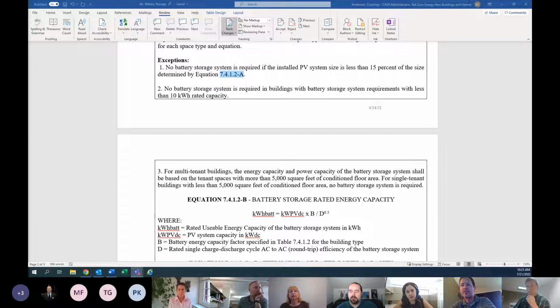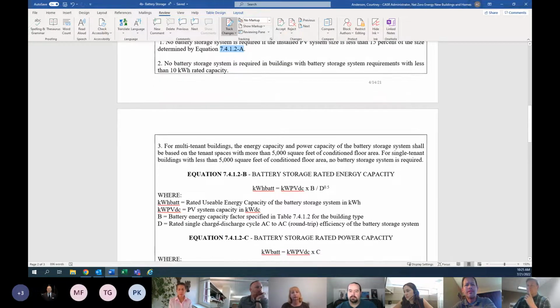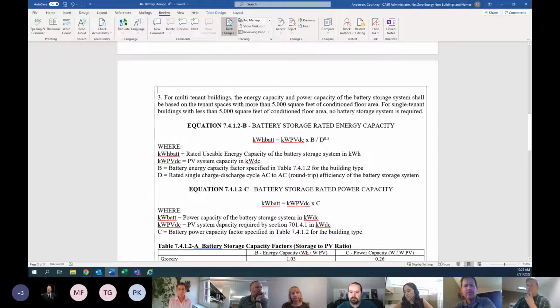I'm sorry, is it possible the number should have been 0.025 kWdc? Because that would make a lot more sense. Right now at 0.25, for 5,000, 6,000, 7,000 square feet, I can have a very large system exempt from the battery storage system. Sorry, that's Exception 1.